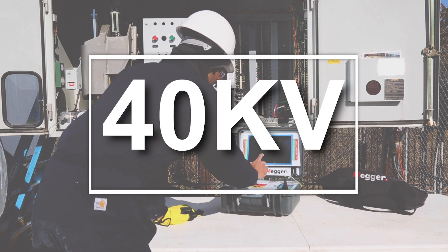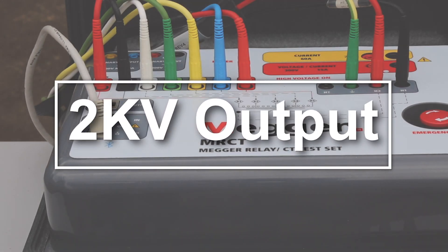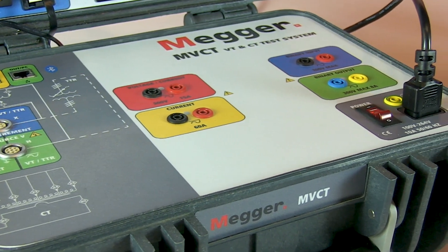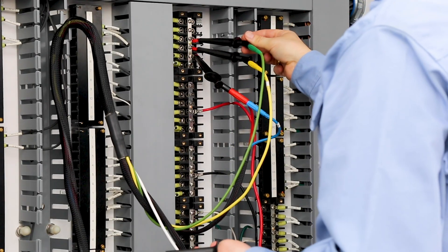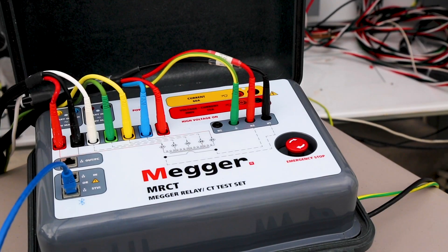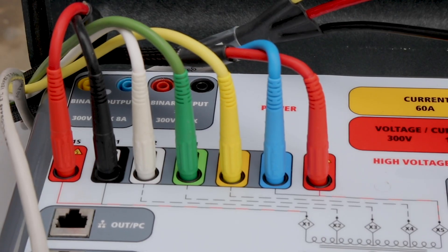The MRCT offers the capability to test both inductive and capacitive coupled voltage transformers with its 2 kilovolt output. Both models are intuitive and easy to use. Connections are simple with MRCT, requiring only two connection points for testing multi-ratio CTs. Press only one button to perform all automated tests on all taps without changing leads.